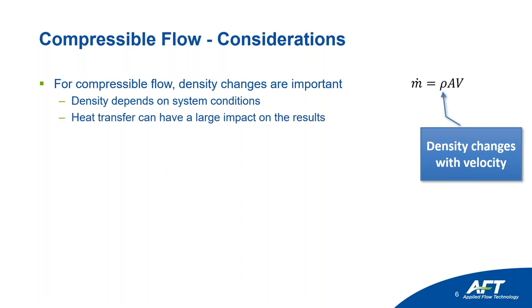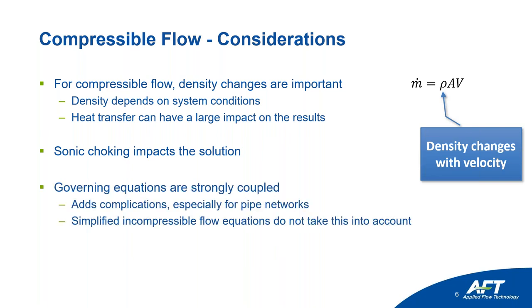Heat transfer will have a large impact as well, especially on density. We also have sonic choking to pay attention to in compressible flow systems — we do not usually worry about that in liquid systems because velocities are so much higher in compressible flow that we actually approach the local sonic velocity. The governing equations are strongly coupled, there are more of them, and it becomes a giant matrix. It gets complicated within one pipe, and you can imagine the complexity with a huge network with compressors and different outflows and inflows. Simplified incompressible flow equations do not take this into account.